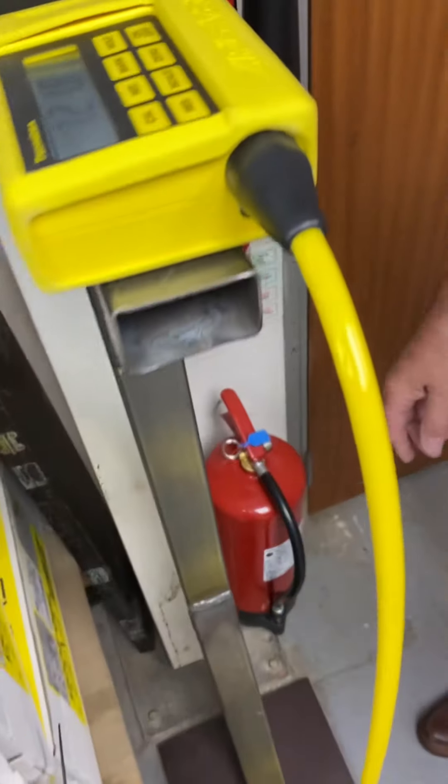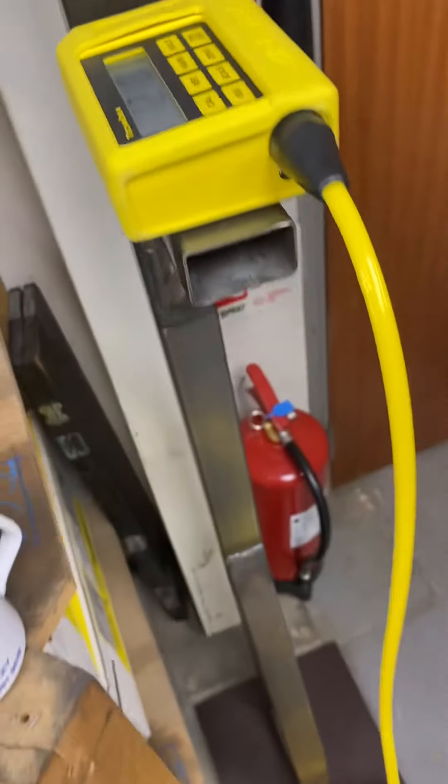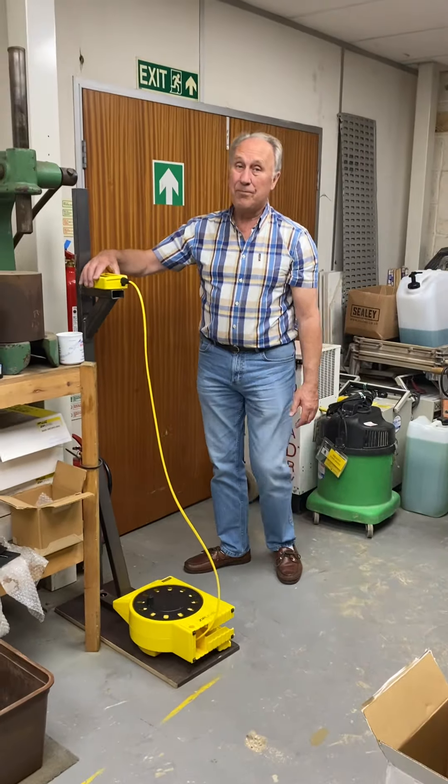As you can see it's on 1218 there, so that's correct. Now if you haven't got a unipod, you can buy one. But if not, you need to have something that's exactly four feet from the floor. We have a test rig that we use in our service room here, and the way we do it is the four feet or 1219 is measured from the base plate, not from the floor.